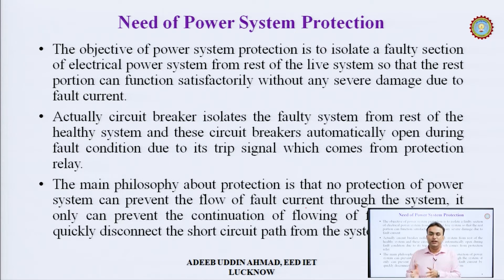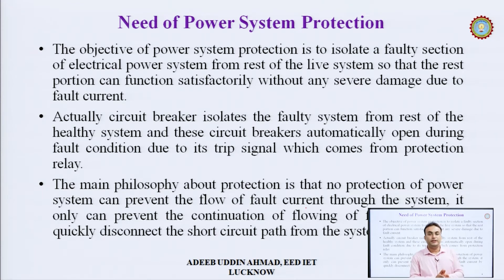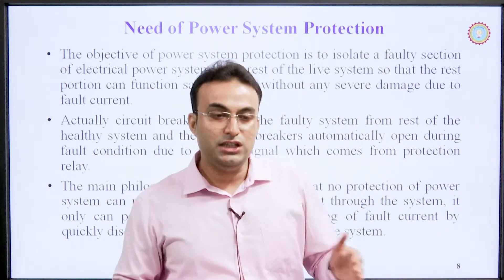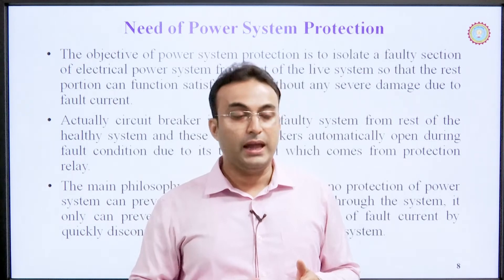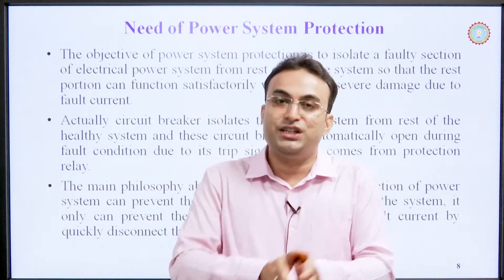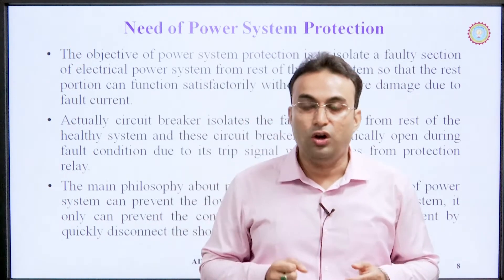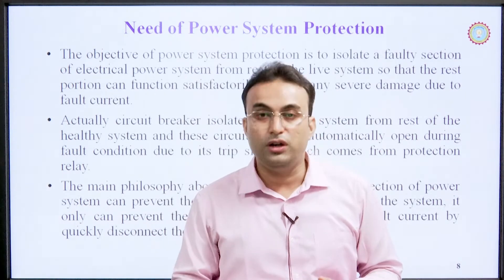The protection relay senses the fault and gives a signal to the circuit breaker, which trips the faulty line to separate it from the healthy line. The main philosophy of protection is that no protection system can prevent the flow of fault current through the system — it can only quickly disconnect the short circuit path. We are not stopping the fault current instantly; rather, we interrupt its continuity by disconnecting the faulty section from the healthy section.